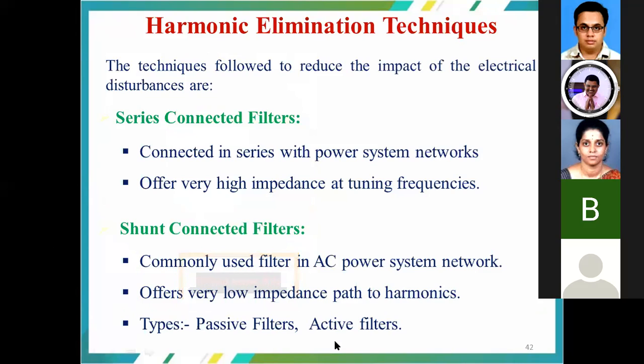So the harmonics elimination techniques: the effective methods to eliminate harmonics problems rely on filters. The first one is the series connected filters, and the second one is the shunt connected filters. In the case of series connected filters, the filters are connected in series with the power system network and offer very high impedance at the tuning frequency, which filters out the unwanted noise or frequencies. The shunt connected filters, commonly used in AC power system networks, are connected in parallel and offer a very low impedance path to the harmonics, thereby eliminating the unwanted signals or frequencies.